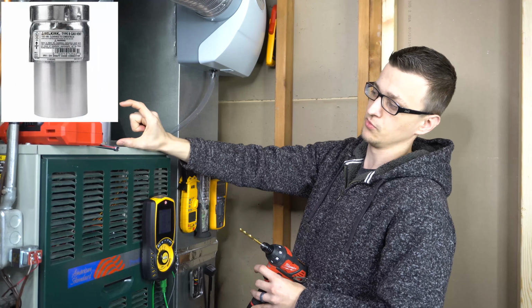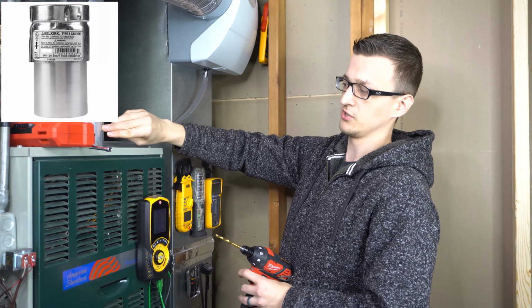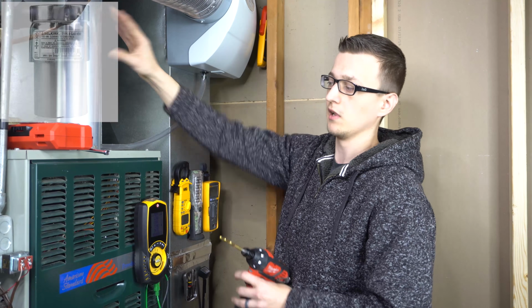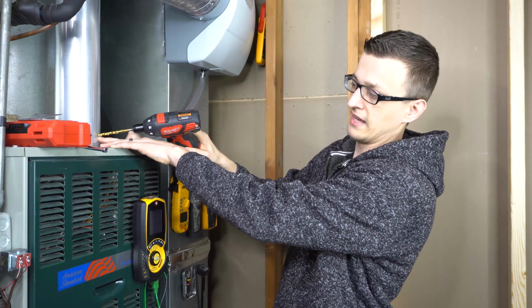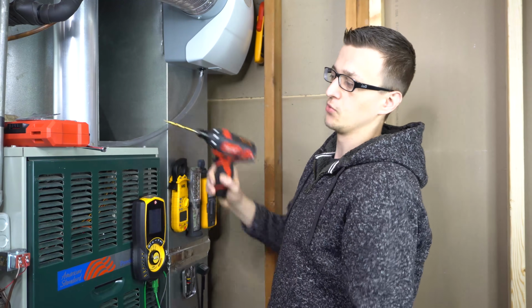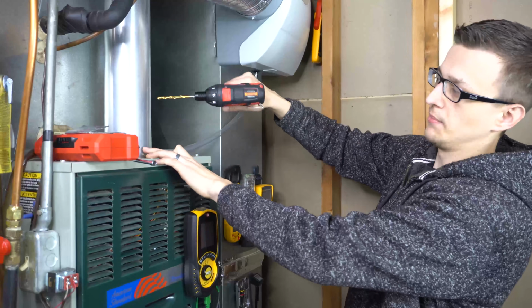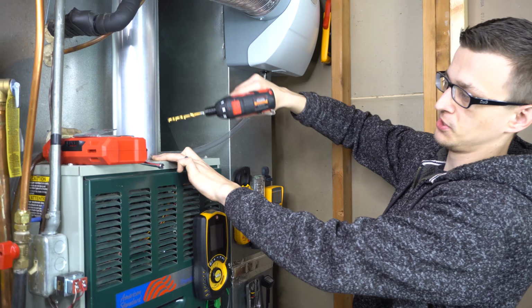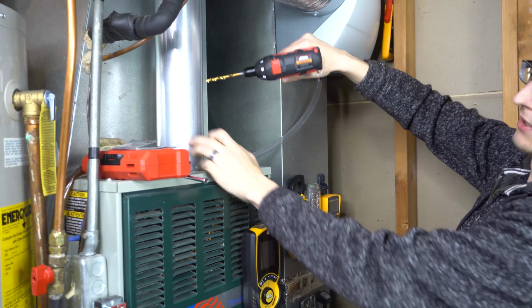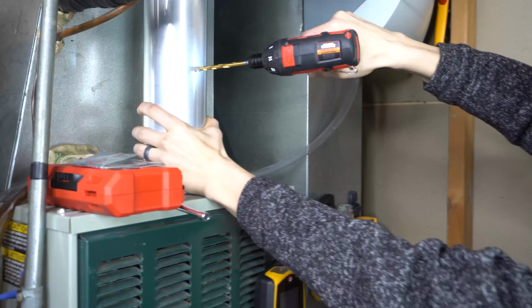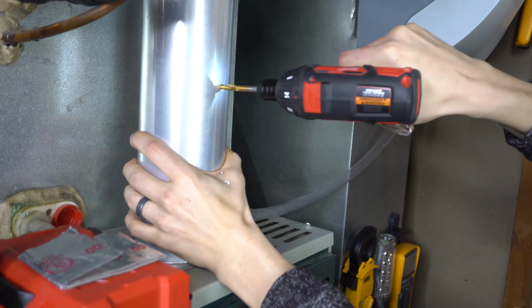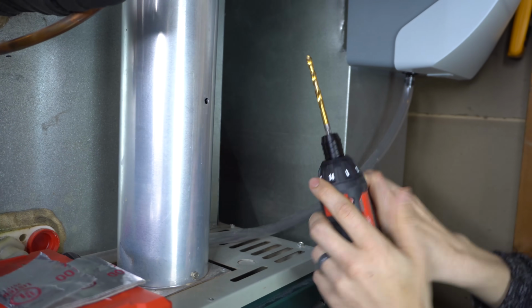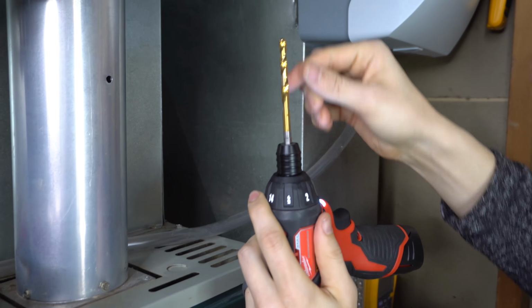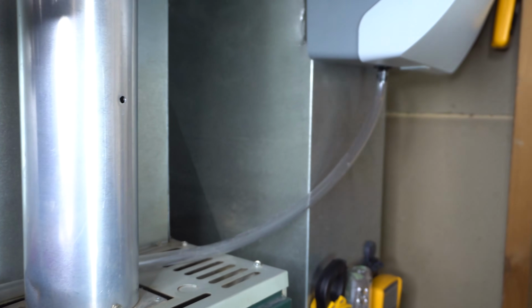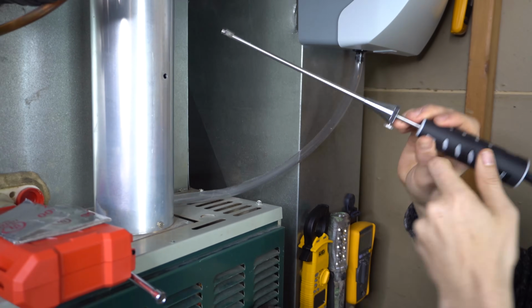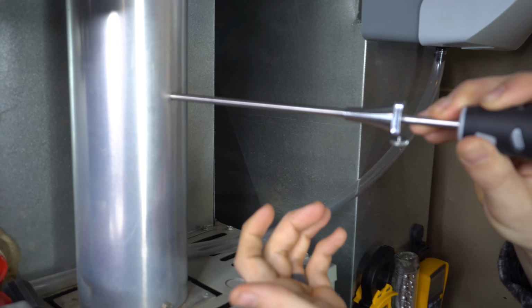So on the bottom section, right where it comes out of the furnace, usually it starts out with a single wall and then goes into a double wall. In that case, you can just drill it right in that transition or that adapter and take your reading from there. So typically I drill a hole somewhere from 6 to 12 inches from the furnace in the vent. So I'll just drill a hole right over here. And the size drill I picked is just slightly bigger in diameter than my test probe. Let's go ahead and see if my test probe fits now. And as you can see, it just goes right in.